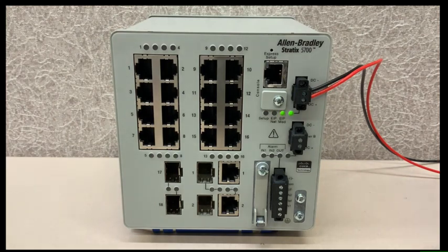Make sure that the power on sequence has completed by verifying the EIP mod and setup status indicators are flashing green. If the switch fails the power on sequence, the EIP mod status indicator turns red. If you do not press the Express Setup button within 5 minutes after the power on sequence is completed, the setup status indicator turns off. However, you can still run Express Setup after the setup status indicator turns off.